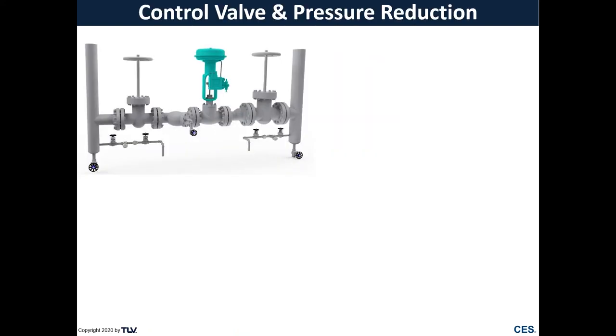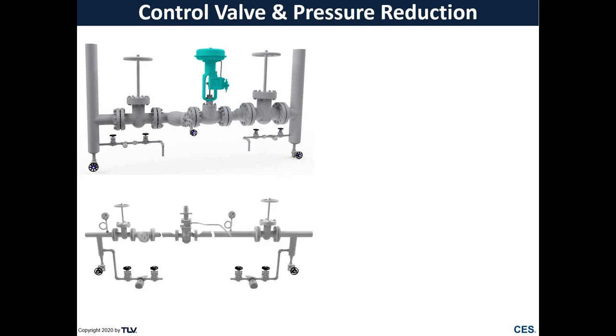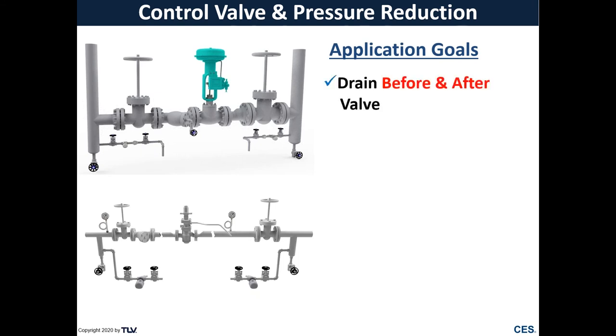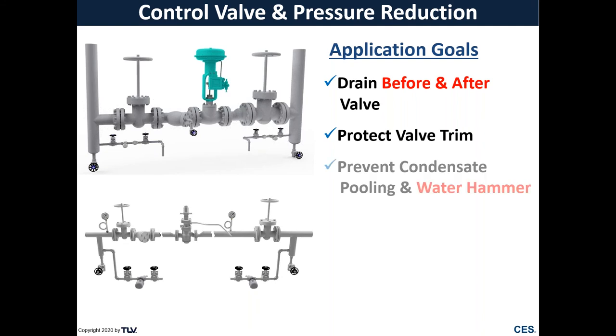Control valve and pressure reduction stations are another important drain point in our condensate discharge location system. The application goals here are we want to drain condensate before and after the valve. That is to really protect that valve trim from erosion caused by condensate. We also want to prevent condensate from pooling when that control valve or pressure reduction valve is closed. A rapid opening of that valve with backed up condensate could lead to a water hammer incident. So we want to avoid that.